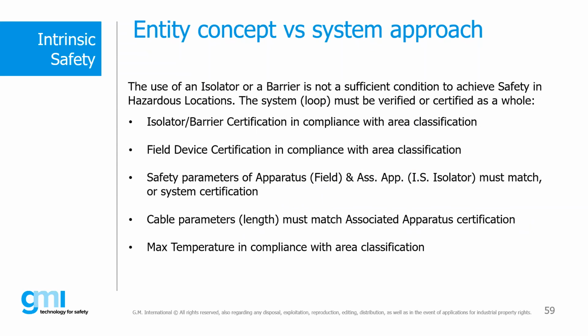The field device certification must be compliant with the ATEX classification. So you cannot use a field device which is certified for zone 1 in zone 0. The other way around, of course, is possible, but not in this case. And the safety parameters for the field apparatus and the IS isolator must match together. We want to tell you later how. Cable parameters must also match the apparatus certification.